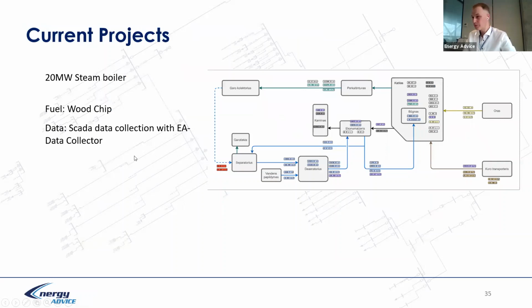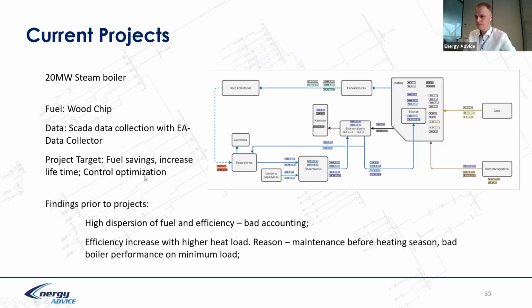Okay, current projects: a 20 megawatt steam boiler on wood chip. Data was collected through Energy Advice data collector software, as I showed previously in the diagram. The targets were fuel saving, increased lifetime, and control optimization. Findings prior to the project: high dispersion of fuel consumption and efficiency, probably bad accounting errors, and efficiency increasing with higher heat load. It's the opposite. Efficiency should increase with lower loads, but not increase with higher loads.